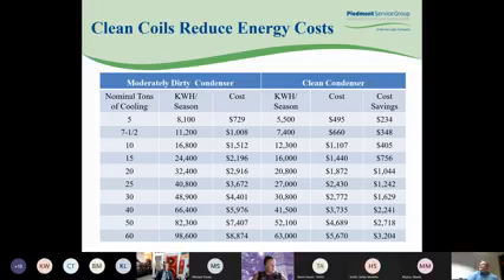The next slide shows a chart put out by Carrier, and it represents the energy savings from washing condenser coils. It compares moderately dirty coils to clean coils. It shows the measurement of the energy consumption in kWh and using 9 cents per kWh. It shows savings of greater than 30% just if you clean your coils.